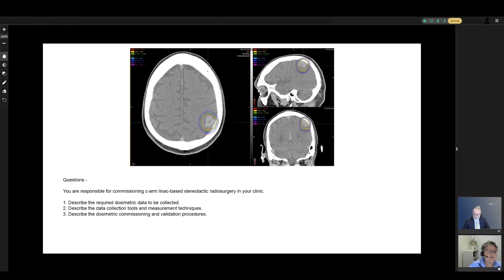Okay, previously you mentioned a few detectors. So tell me a little bit about some pluses and minuses to each of these detectors in the context of these small fields. And pick one, and then tell me a little bit about how they would work and how they're affected by the small field sizes. Okay, so let me start with a micro ionization chamber. They're really small, so they may be subject to extra currents, for example, from the cable or the stem effect, and also prior irradiation. And they're very small. So the central electrode sometimes is made out of high-Z material, which means they can over-respond in your chamber. And that's something you need to be careful about.